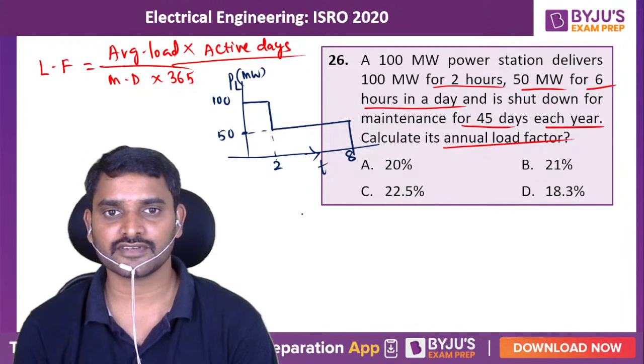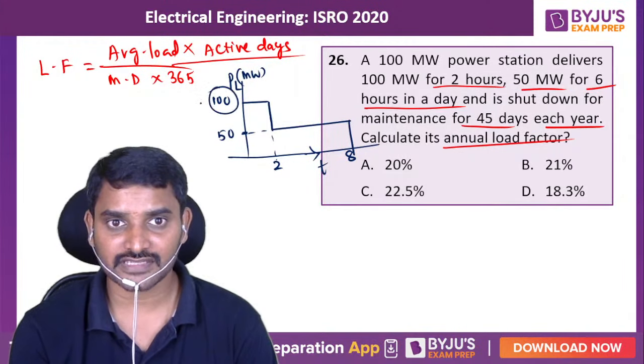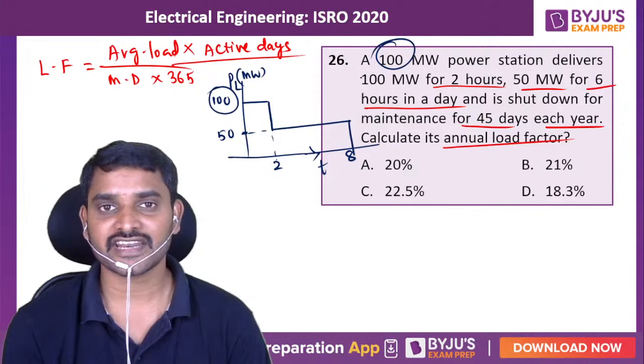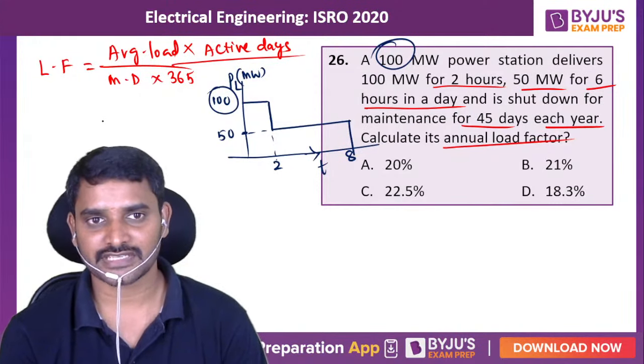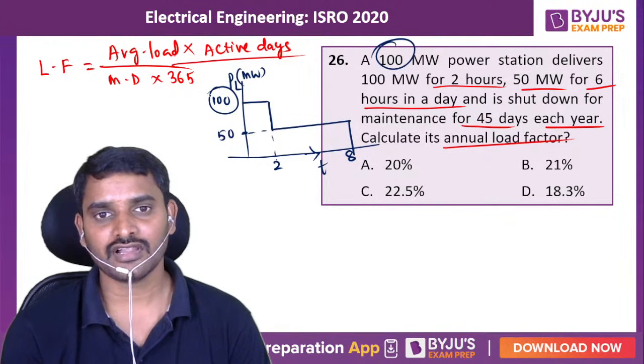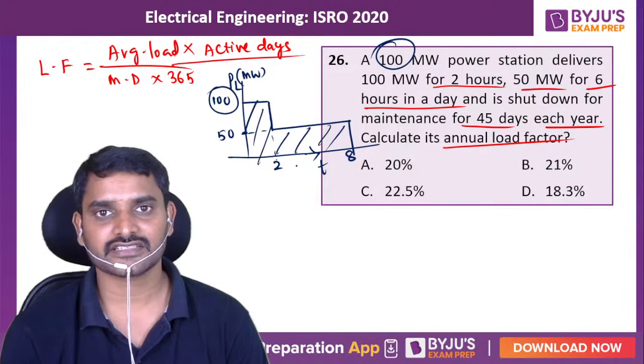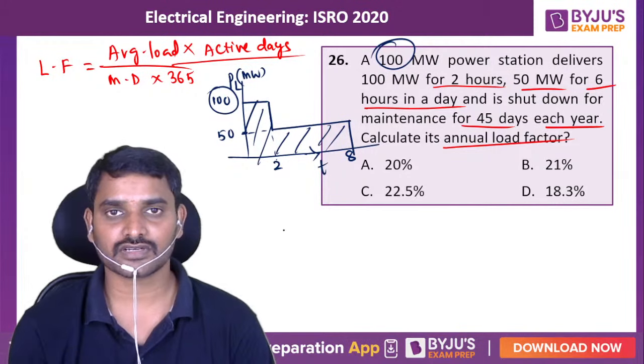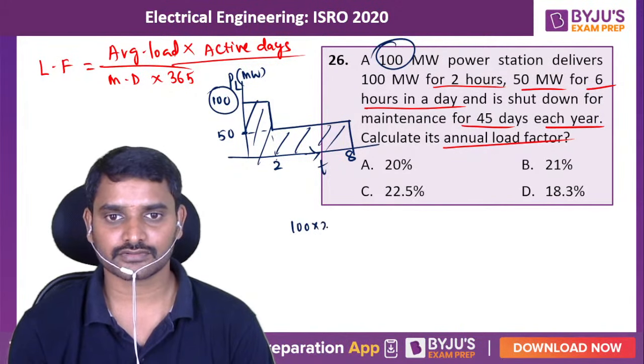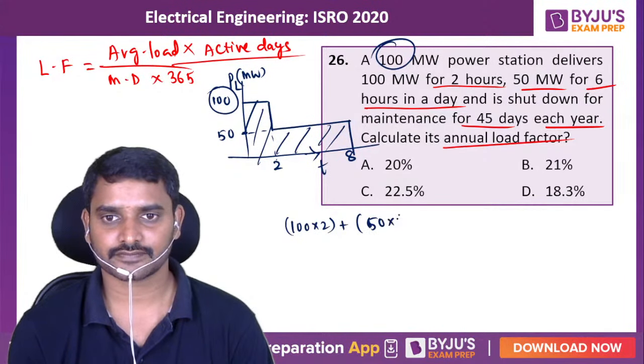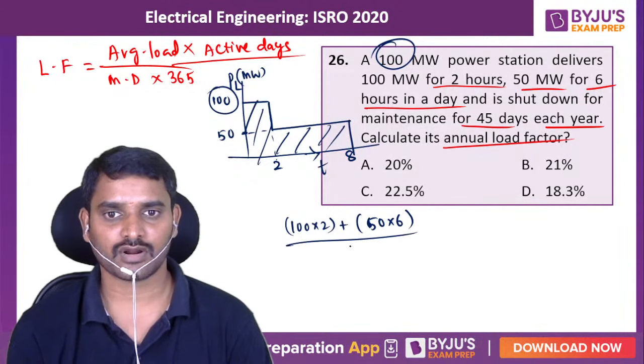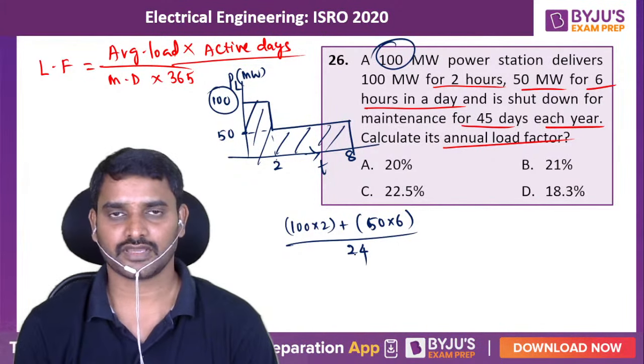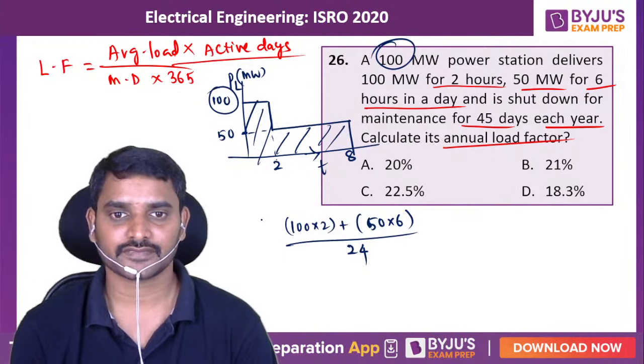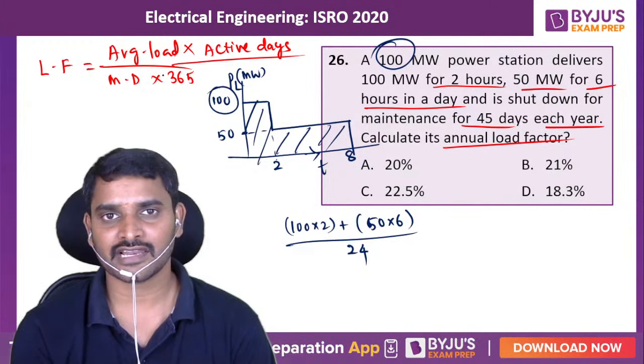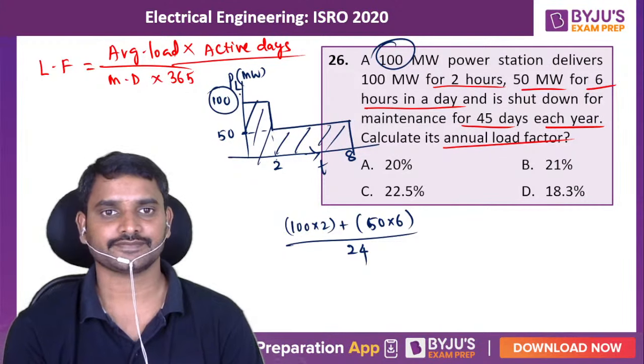So this is the load curve you are going to get. From the load curve you can pick the maximum demand. So you cannot directly take up the generator capacity here. To solve the average load, you can take up the area under this load curve. So what is the area under the load curve? You are going to get 100 into 2 plus 50 into 6. Only for 8 hours duration out of 24 hours duration. Rest of the time anyhow it is going to be shut down, right? So this is my average load. So substitute that value here and solve it.